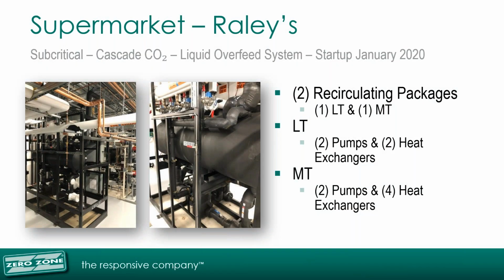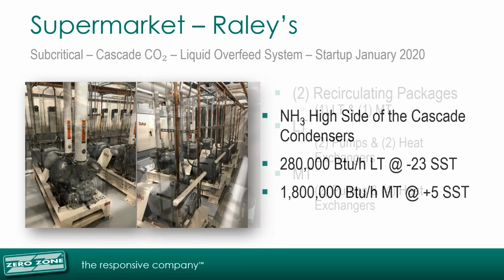We were fortunate to be part of Raley's newest store. Their new store in Sacramento utilized a CO2 liquid overfeed system with 2 recirculating packages. The low temperature recirculating system had 2 pumps for pumping liquid CO2 to the cases and 2 cascade heat exchangers. The medium temp system also used 2 pumps, but utilized 4 heat exchangers. The system started up in early 2020.